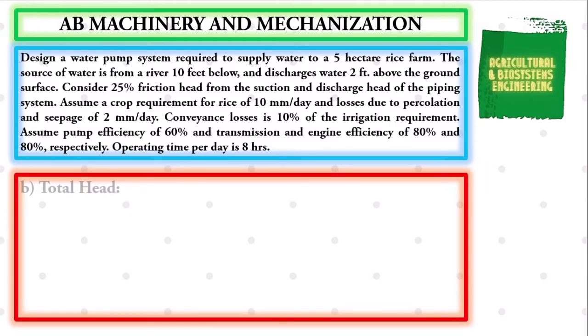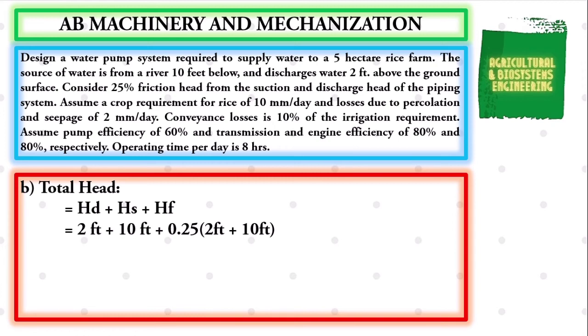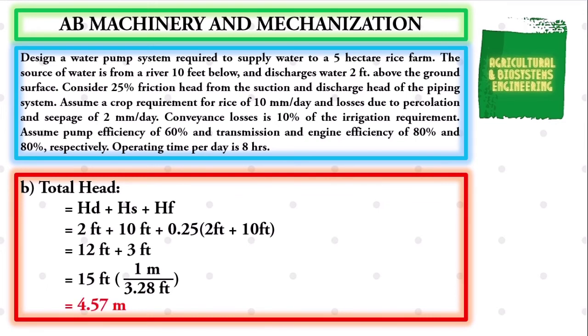The next value to solve is the total head. The formula is: total head = discharge head + suction head + friction head. Substituting: 2 feet + 10 feet + 25% of (2 + 10 feet) = 12 feet + 3 feet = 15 feet. Converting to meters using 1 m = 3.28 feet, the total head is 4.57 meters.